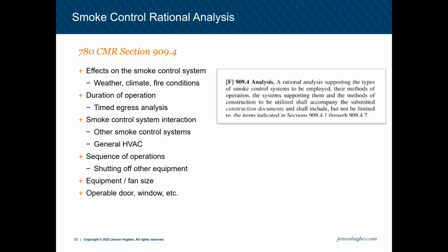And that gets really detailed and really should be thought about for something like a lab building, where you can't just shut off all the exhaust and all the supply during a smoke control event, because lab fume hoods need to generally keep on running all the time to some CFM and some level. The rational analysis will hopefully finalize the equipment and fan sizes, so people can take those fans, start looking at product data sheets, start looking at cut sheets, start looking at electrical distribution for the fans, and then also operable door and windows.